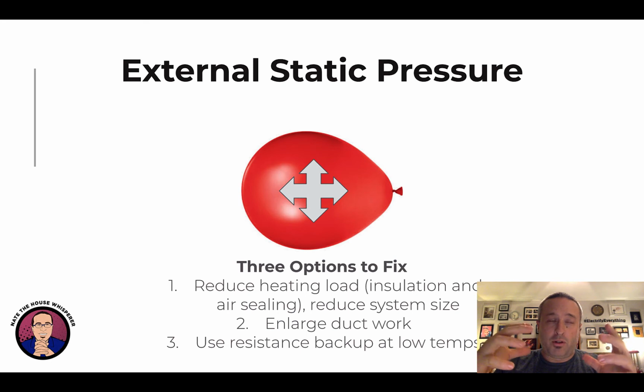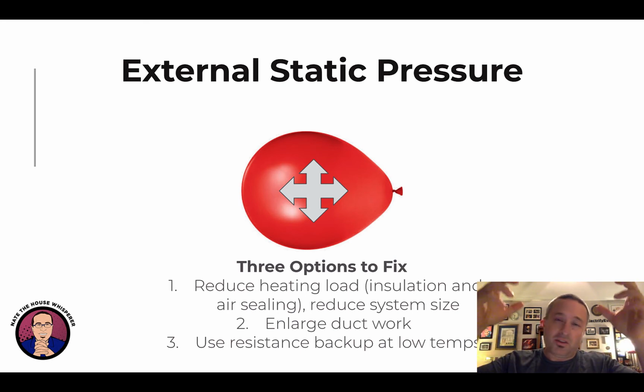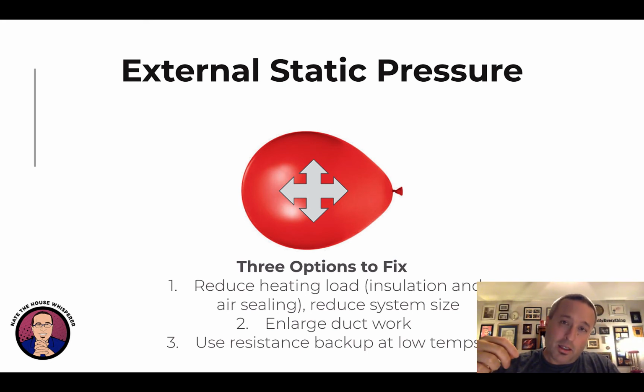But if you need to enlarge ductwork, particularly that goes up inside a wall, good luck—that's some pretty major surgery. In general, what we find is if you downsize the systems and right-size the duct systems, that oftentimes works. But you have to measure, you have to test, you have to know what you're doing.